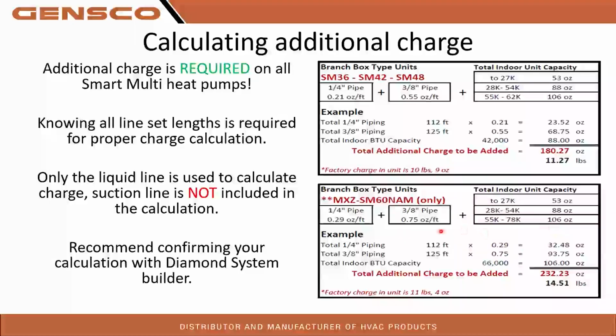So there's 106 ounces. In our example right here, they have 112 feet of 1/4-inch pipe times 0.29 equals 32.48. Our 3/8, 125 feet times 0.75, 93.75, plus our indoor capacity of 106, because we're between that 55 and 78 for this example, 66,000 right there. So there is your total additional charge, 232.23 ounces or 14.51 pounds additional charge for your system.